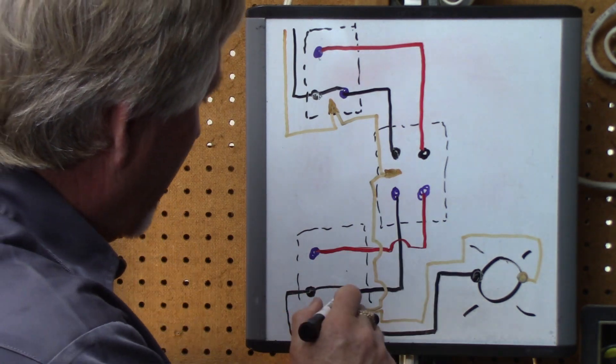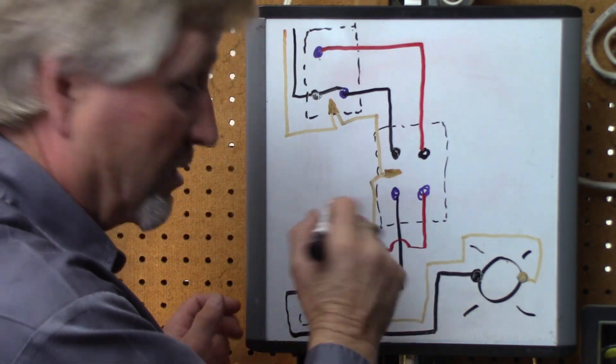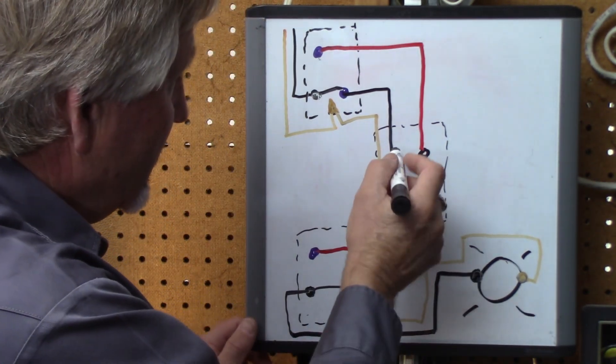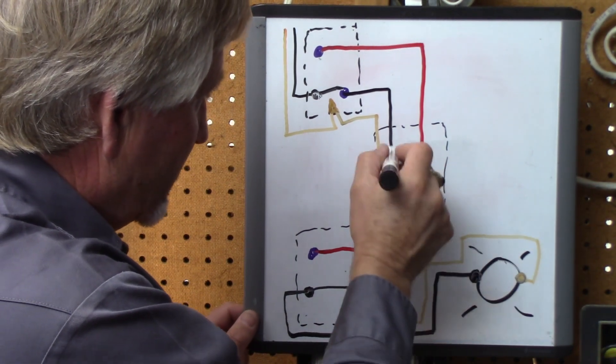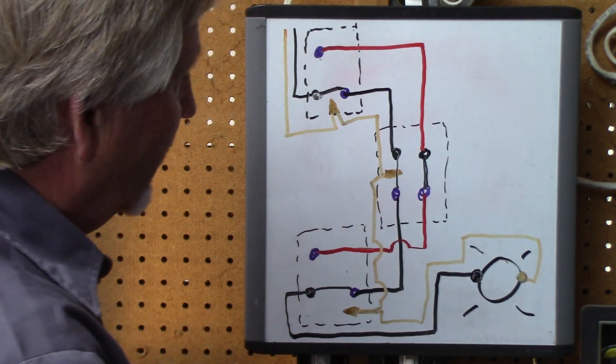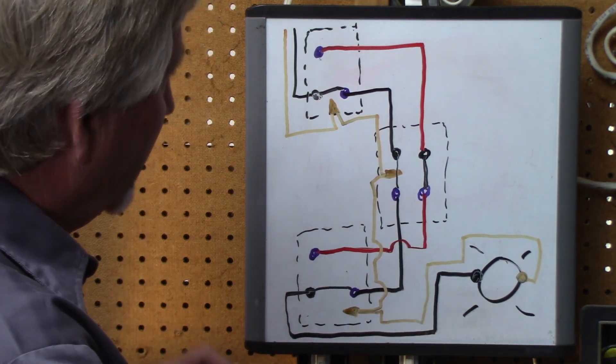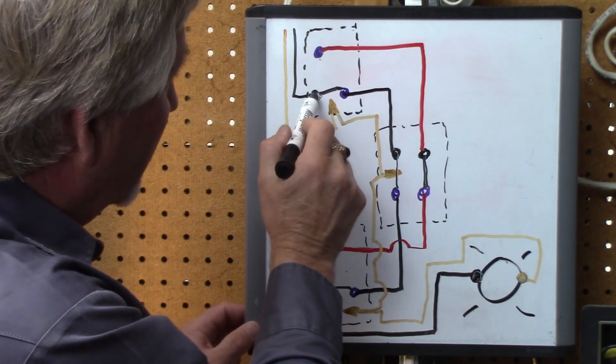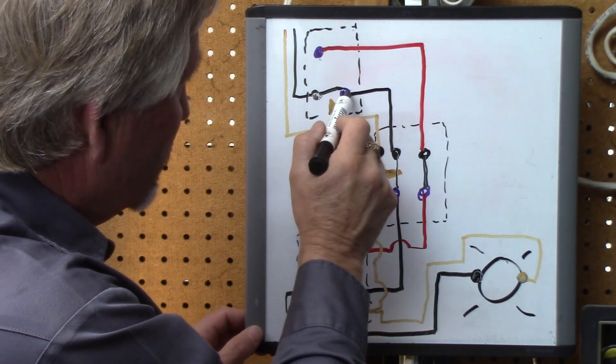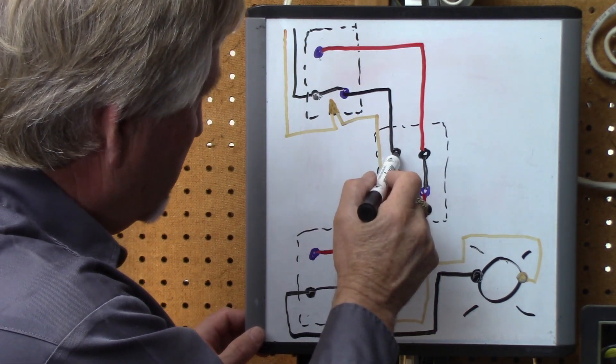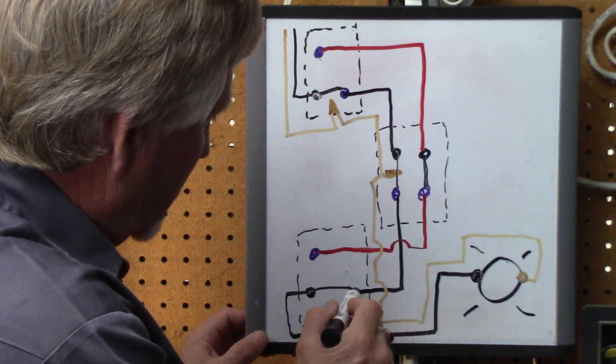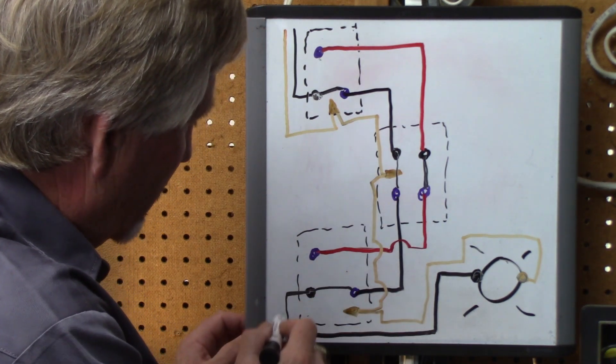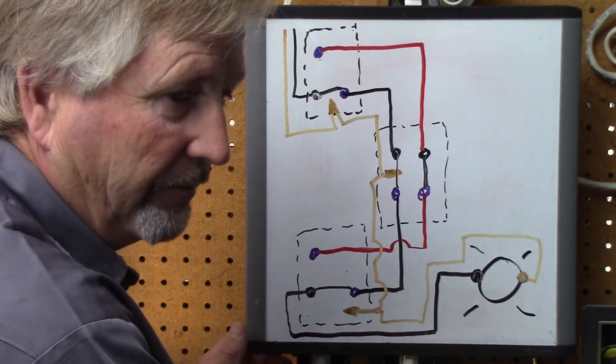But let's see what happens in the 4-way switch. So what it does is it is either going to be in one position. It connects these two sets of terminals together, okay? So let's follow it through again. Power coming in. First 3-way. Common. Switches down. Comes down on this black traveler wire. Goes through the 4-way switch. On to the 3-way switch. That switch is in the down position. And your light is on, okay?